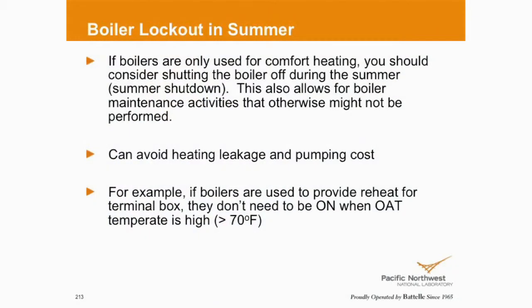Yeah, that's awesome. So the other thing is, this may or may not be in the slides, but is there anything I can do in the summertime? I've got to have reheat in the building. My steam or my hot water system is serving radiation. Can I valve it out? If it's steam derived, can I shut down steam that's going to my preheat coils, my other heating coils? I don't need to worry about piping hot water to all these coils. I just need it for my reheats.